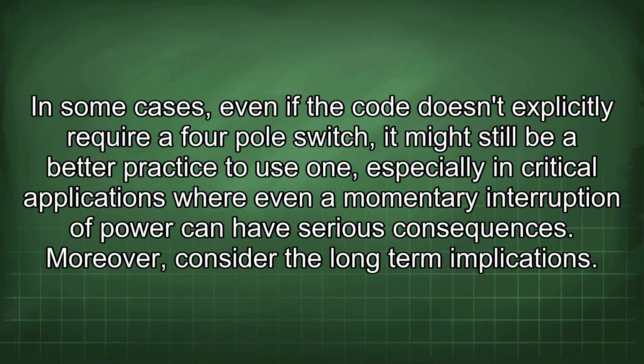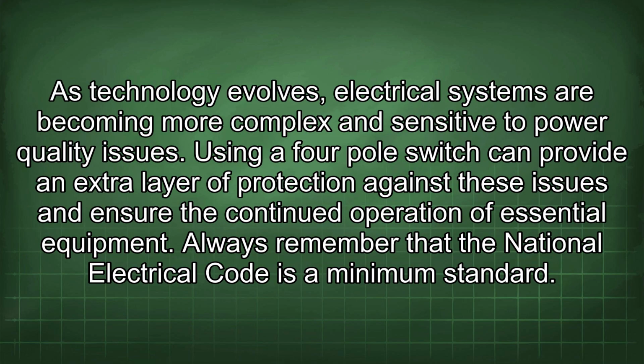In some cases, even if the code doesn't explicitly require a 4-pole switch, it might still be a better practice to use one, especially in critical applications where even a momentary interruption of power can have serious consequences. Moreover, consider the long-term implications. As technology evolves, electrical systems are becoming more complex and sensitive to power quality issues. Using a 4-pole switch can provide an extra layer of protection against these issues and ensure the continued operation of essential equipment.